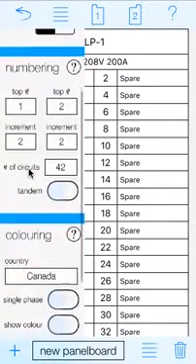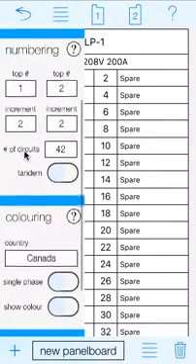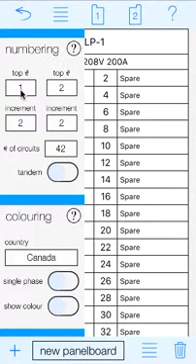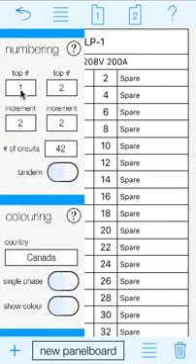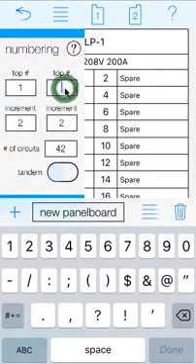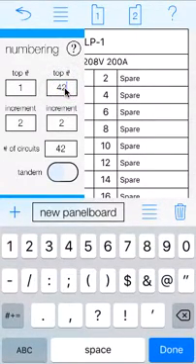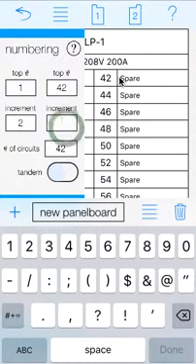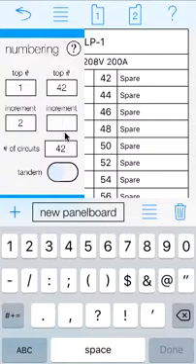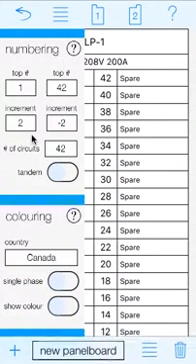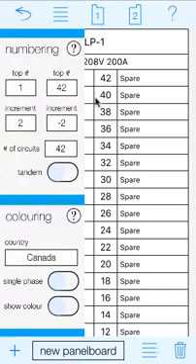Now we go to our circuit numbering. So you'll be able to do your circuit numbers wherever you want, from high to low or low to high sequential on one side. What you do is you set your top number. So let's say we can set our top number on the right side to 42. And now it starts at 42 and increments by 2. But you can change your increment, so you can change your increment to minus 2. And now it'll count down.